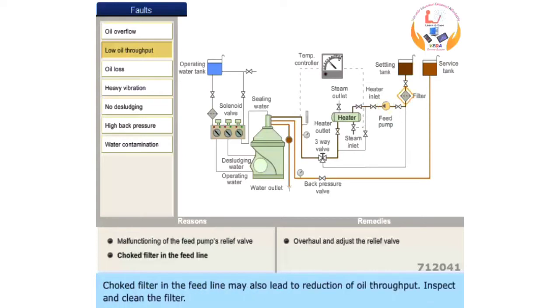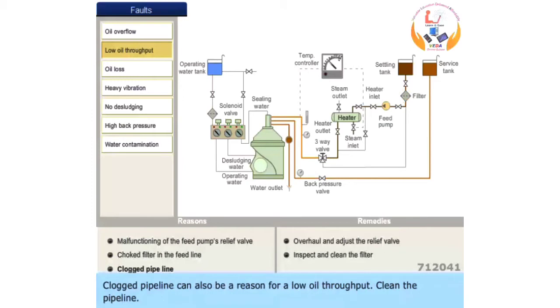Choked filter in the feed line may also lead to reduction of oil throughput. Inspect and clean the filter. Clogged pipeline can also be a reason for low oil throughput. Clean the pipeline.